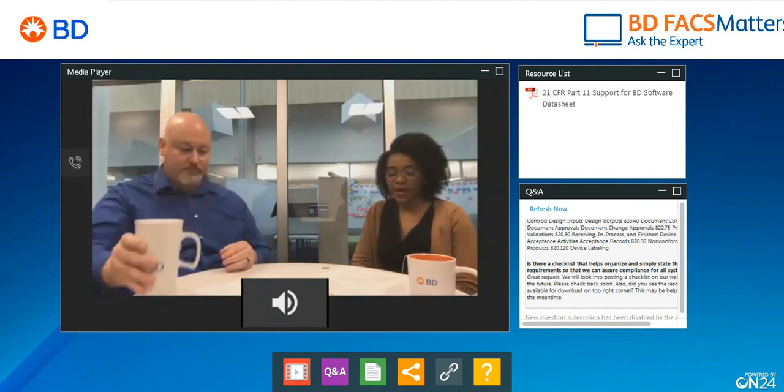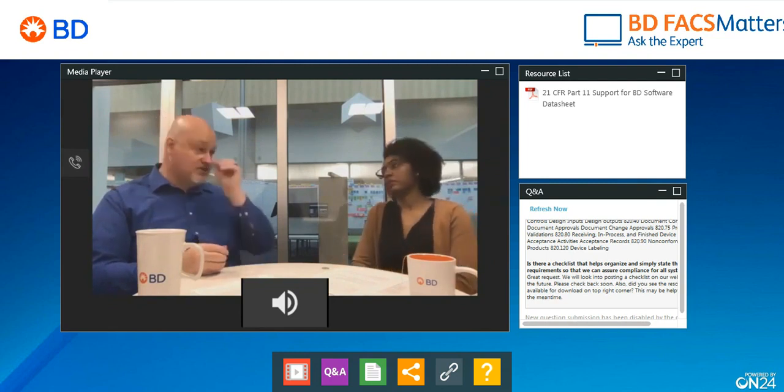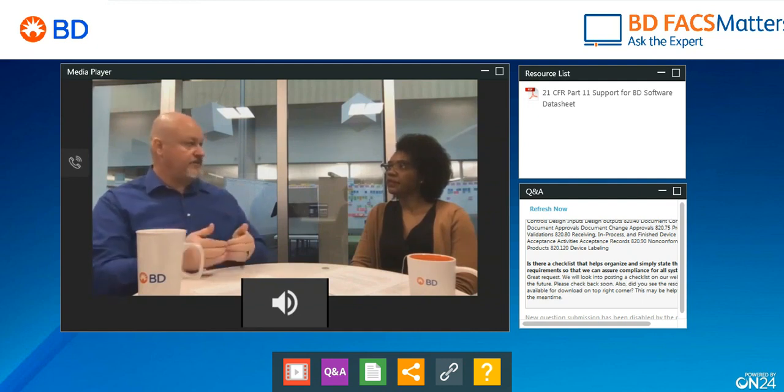So I want to ask about electronic records. Sure. Is any kind of data that is generated on a computer considered an electronic record for Part 11? No. As we talked about, you have to have a predicate rule that says these records, this data you're generating, is required to be provided to the FDA. Doesn't mean it's going to be provided to the FDA, but let's say you have a system where you're doing manufacturing and you're tracking non-conformances of product through a system. So you're generating data and you're manually inputting records and you're routing all the information electronically and having people sign off. That's clearly outlined in 21 CFR 820, which is the quality system regulation, that is required to be maintained.